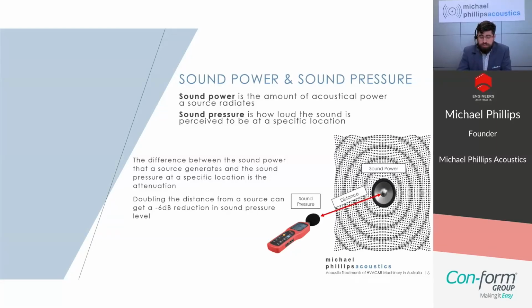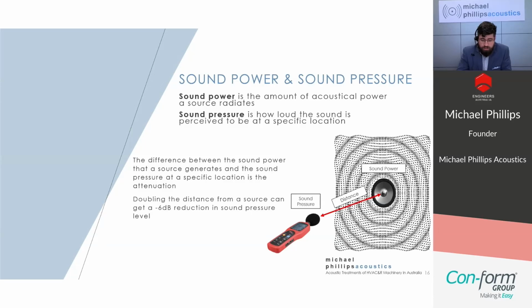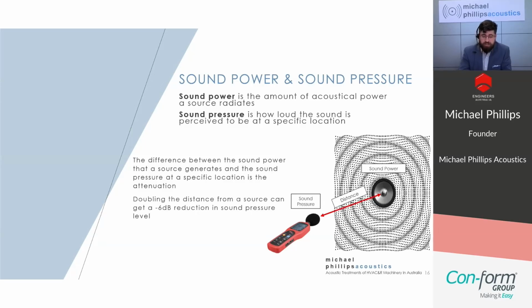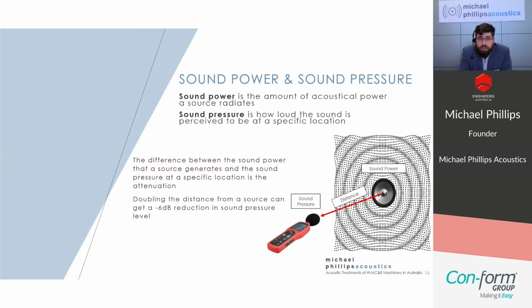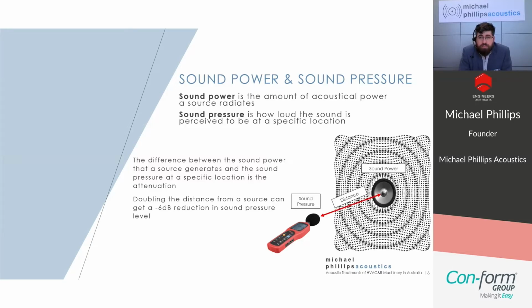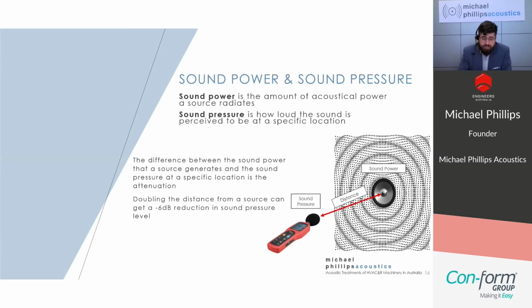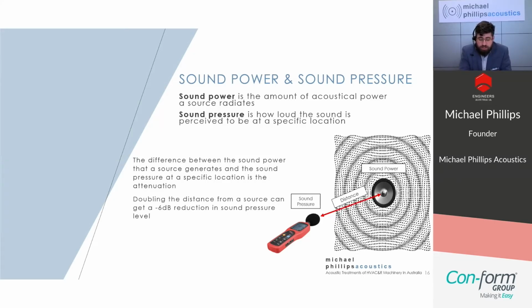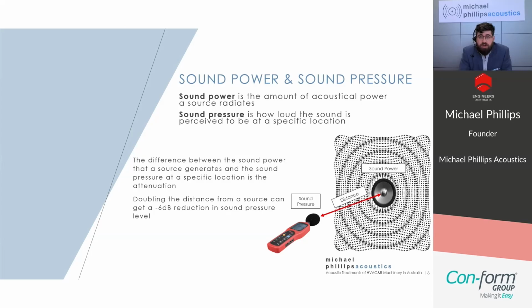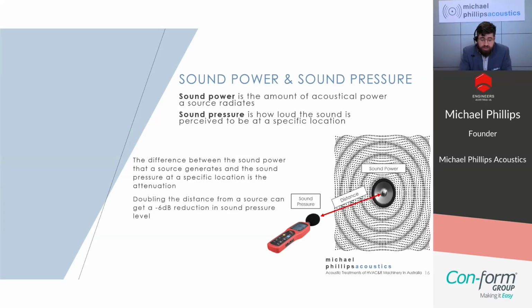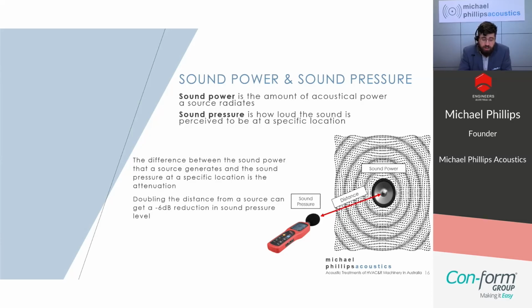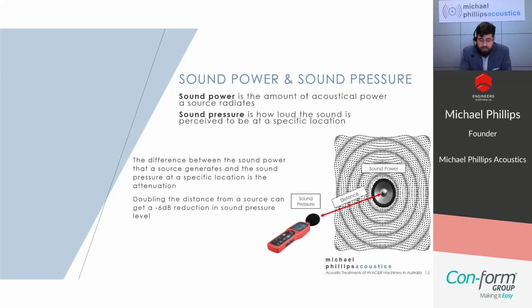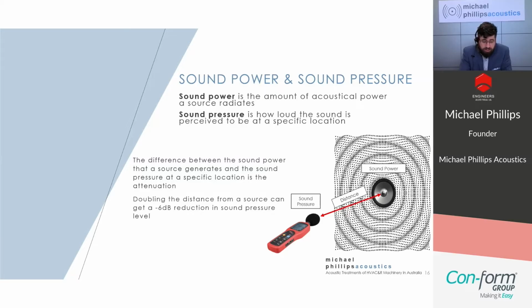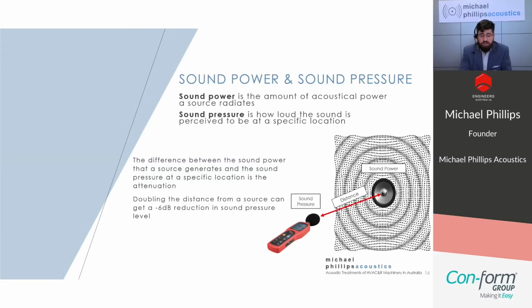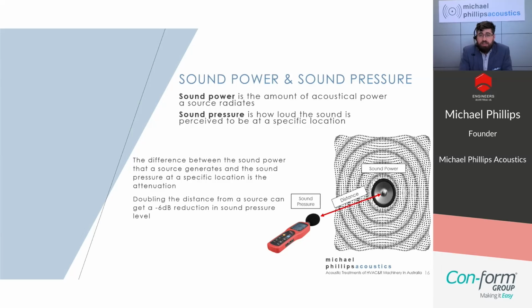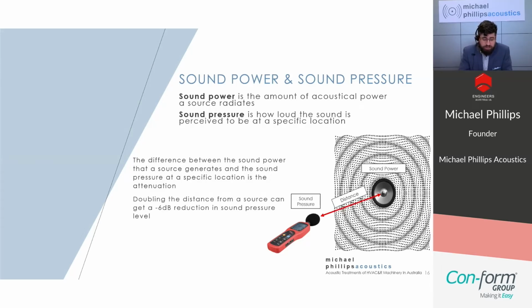So an important distinction to make here is the difference between sound power and sound pressure level. You may have heard the two being used before. So sound power is the amount of acoustical power a source radiates. So essentially this is what HVAC&R equipment generates. And sound pressure is how loud the sound is perceived to be at a specific location. So this can be a noise-sensitive receiver, such as a residential property or nearby commercial premises.